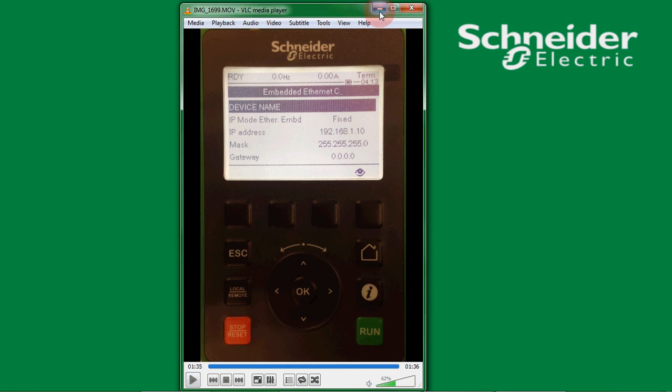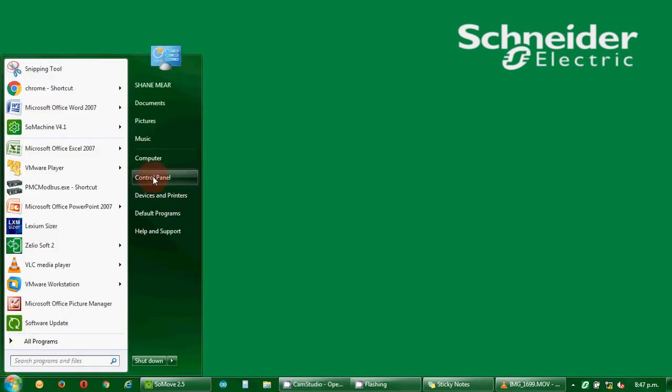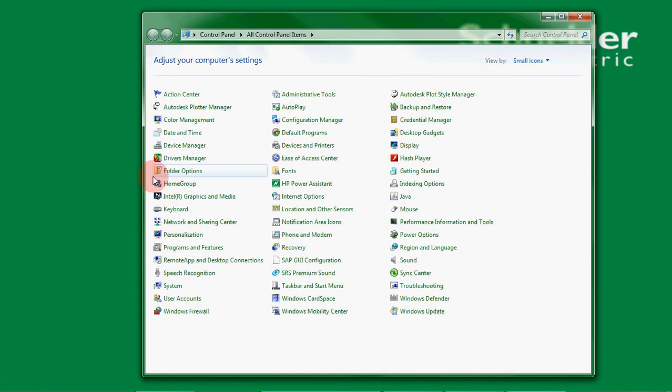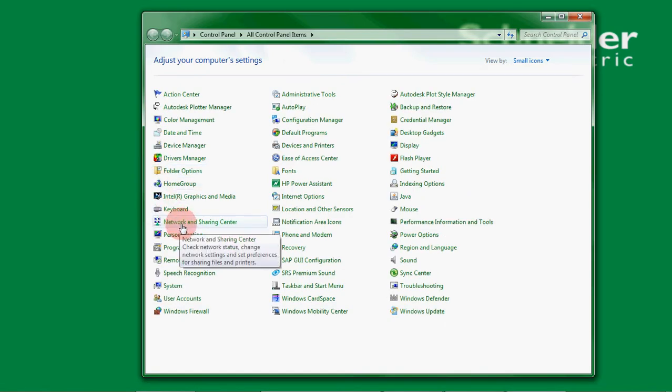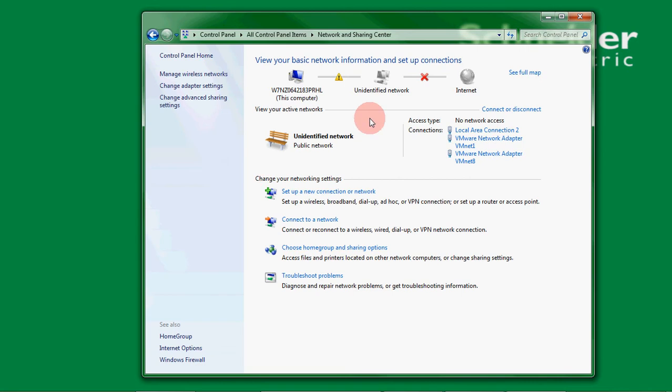That's the VSD side done. We now need to set up the PC with a static IP address by pressing the start button, going into control panel, and then selecting network and sharing center. You then need to look for local area connection. If it's not there you've either not connected the cable correctly or the VSD's off. Make sure those two things are done and you should see the option there.